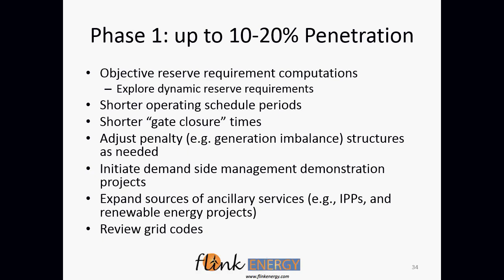So standards for the inverters, for example, to require them to have certain attributes, like providing inertia. I remember early on at PacifiCorp, we had a bunch of wind in southeastern Washington, and the standard for the wind turbines was that if the voltage went to zero—which happens, like if a tree falls onto the power line and it gets grounded, so the power goes away—the wind project was required to turn itself off. But what commonly happens on the transmission side is a limb hits a power line, it explodes or burns up, and the problem goes away. They have circuit breakers that open up, interrupt the power, then wait a bit and try to reclose—doing that 2 or 3 times before giving up and leaving the power off. Well, the wind projects were always just going off, because they had that requirement.